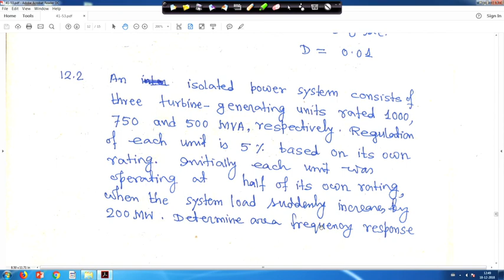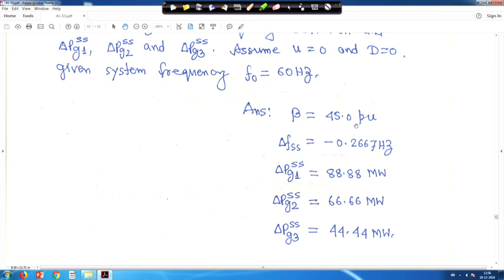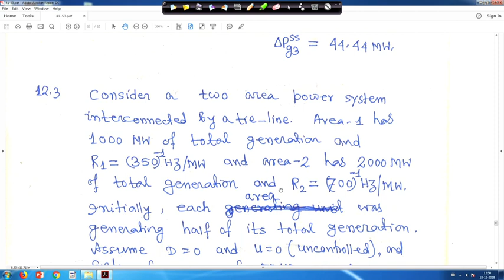The second example is: an isolated power system consists of 3 turbine generating units rated 1000, 750 and 500 MVA respectively. Regulation of each unit is 5% based on its own rating. Initially each unit was operating at half of its own rating. When the system load suddenly increases by 200 megawatt, determine the area frequency response. The answer is given, beta is given, where beta is the area frequency response characteristic, and all the answers are given. Now, the next problem you will do yourself.